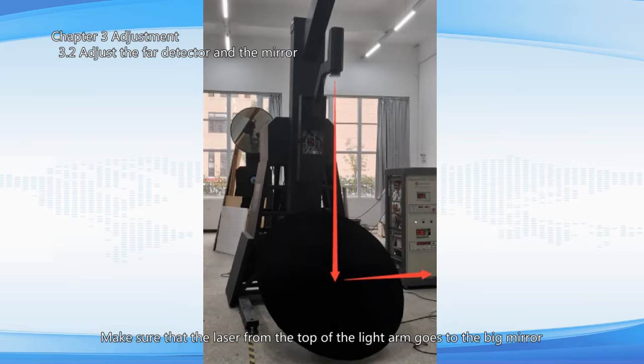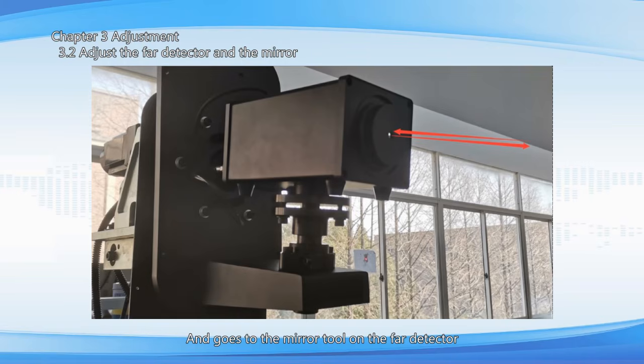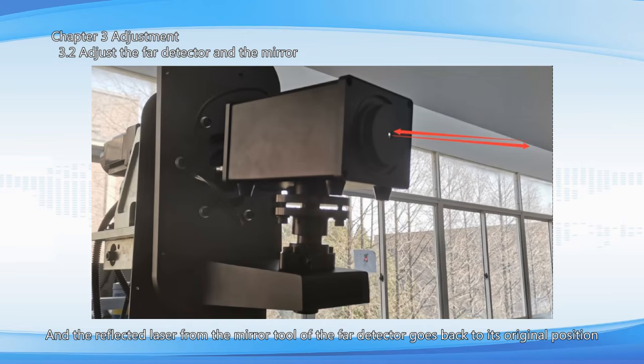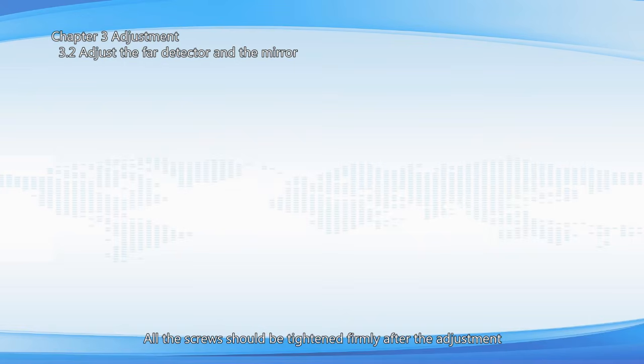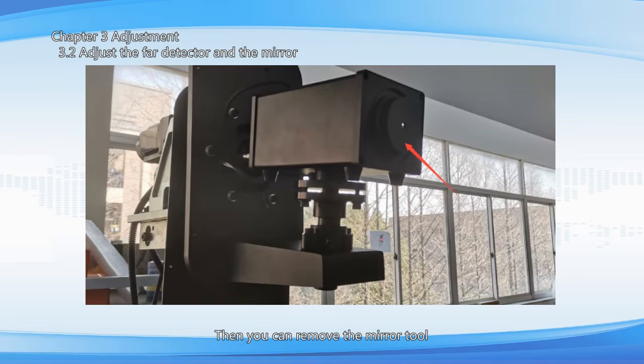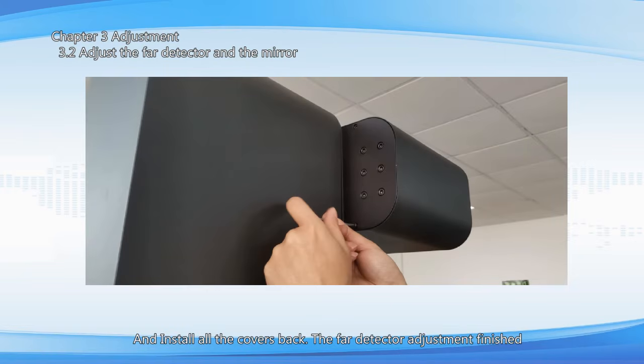Make sure that the laser from the top of the light arm goes to the big mirror and goes to the mirror tool on the far detector. And the reflected laser from the mirror tool of the far detector goes back to its original position. All the screws should be tightened firmly after the adjustment. Then you can remove the mirror tool. Install the sleeve back to the far detector. And install all the covers back. The far detector adjustment finished.